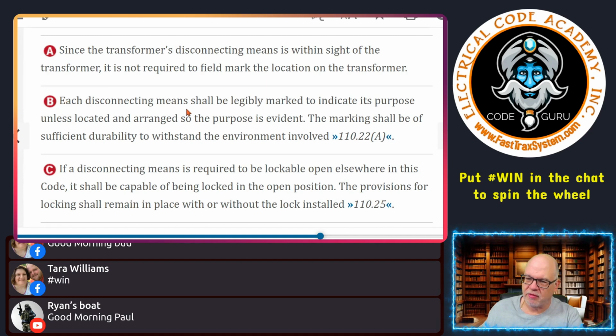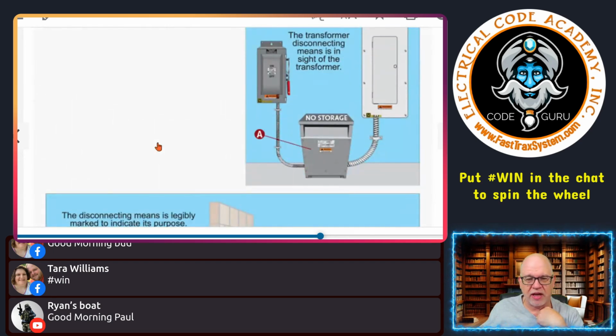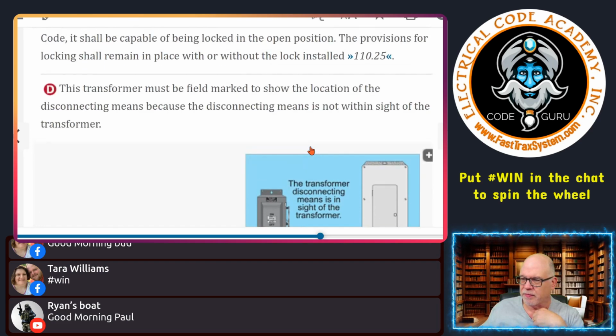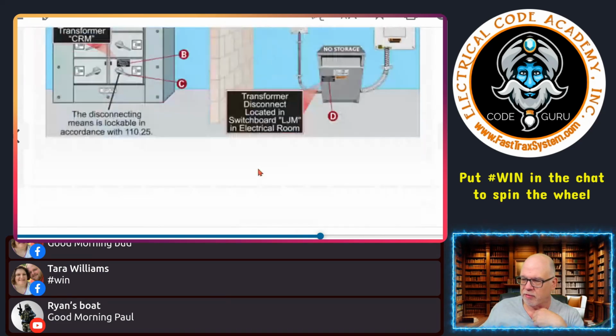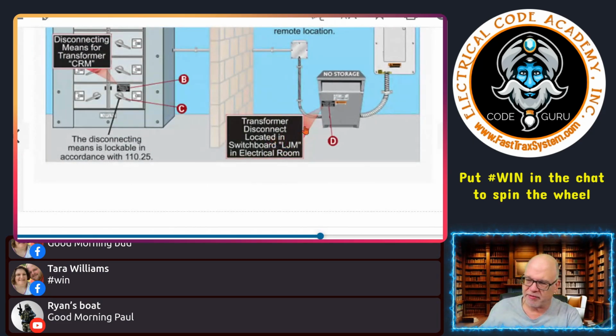Each disconnecting means shall be legibly marked to indicate its purpose unless located and arranged so the purpose is evident. We just talked about that, and that is your 110.22(A). The markings must be of sufficient durability, which means you're not going to be using inkjets. You're not going to be using just a peel and stick, because these get hot and that label could just fall right off. This label right here, typically it's something phenolic, something that can handle the heat and the environment it's exposed to. All those things are covered in 110.22.